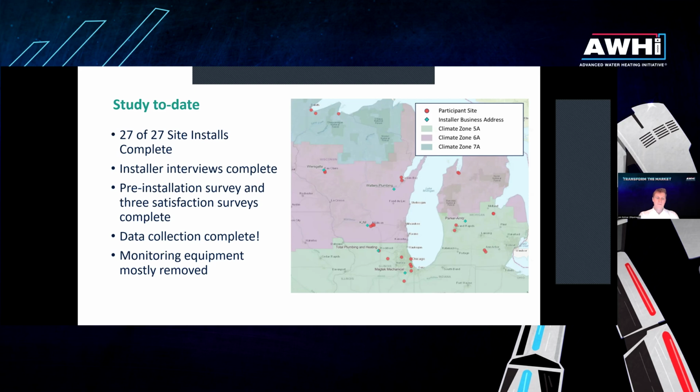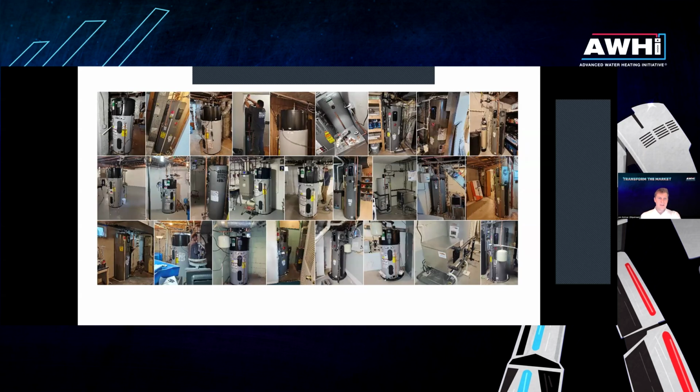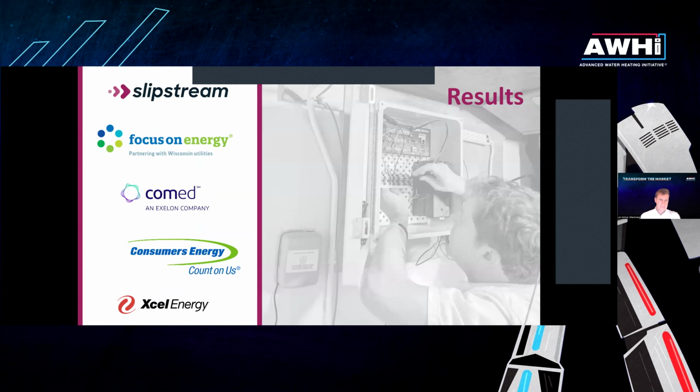We also did 4 satisfaction surveys: on their prior water heater, then a survey 1 month in, a survey at the end of winter, and a survey at the end of summer, which all the results have not come back for yet, but we're excited to see what people think on that one. We had 3 participating manufacturers with 4 types of units deployed. We deployed some of the Rheem dedicated circuit models that Kevin mentioned, as well as shared circuit models. We had A.O. Smith models, 10 of those in the study, and 1 Nyle split system in the study. Here's a picture of all the many basements that we have visited across this work.